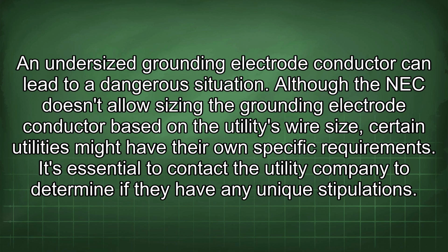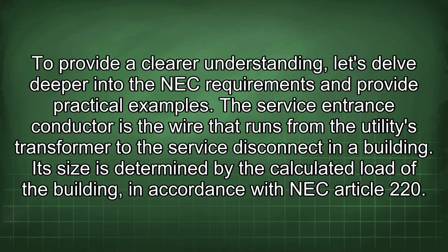Although the NEC doesn't allow sizing the grounding electrode conductor based on the utility's wire size, certain utilities might have their own specific requirements. It's essential to contact the utility company to determine if they have any unique stipulations. To provide a clearer understanding, let's delve deeper into the NEC requirements and provide practical examples.